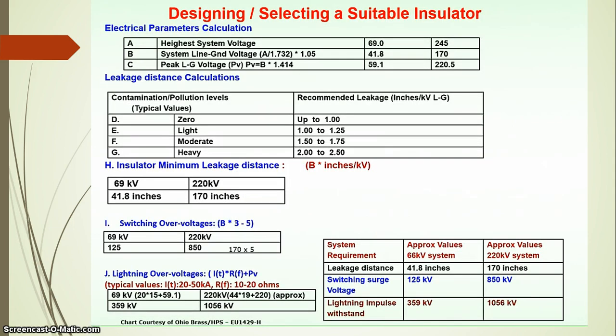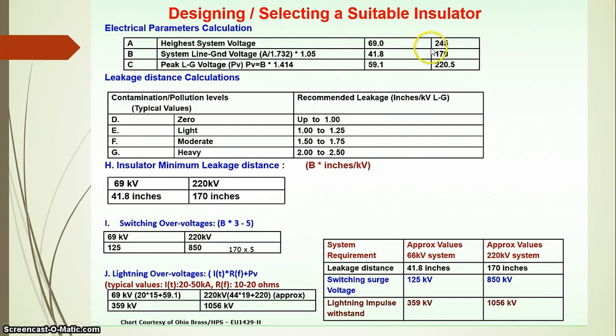Now we look at a typical system for designing and selecting a suitable insulator. The various criteria for insulator selection begin with electrical parameter calculation. For a 220 kV system, the higher system voltage is 245 kV — the maximum voltage level. The system line-to-ground voltage, or phase voltage, is calculated as: maximum voltage divided by root 3, multiplied by 1.05, which gives 170 kV.